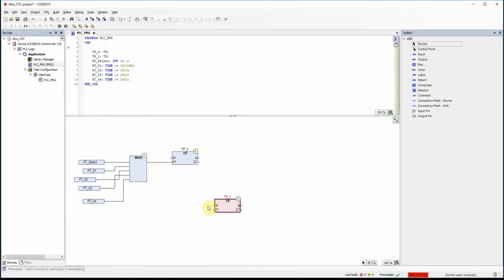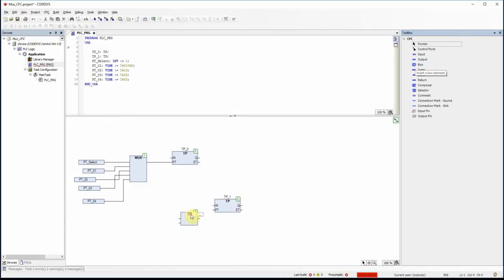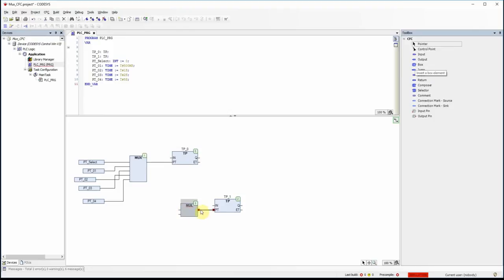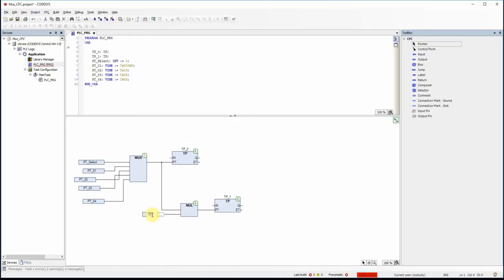I want to create a blinking output. For the second pulse timer I'm using a MUL box which receives the output of the multiplexer, multiplies it by 2, and uses the result as the preset time for the second timer. The output of the MUL box is connected to the PT input of the second pulse timer, with the constant value 2 as the second input.